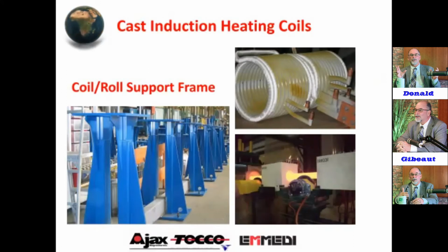And we did that because once upon a time, all of the coils had end plates and a mechanical structure. And the end plates that see all the heat and the thermal stresses were made out of asbestos. Well, that's been outlawed in most manufacturing, just about all, I think. And so the replacements, the NAD11, or the Transite 2, as they call it, are all a silica-based material that doesn't have the mechanical or thermal properties. So we tried it for quite a few years, and then we punted to this cast brick design.